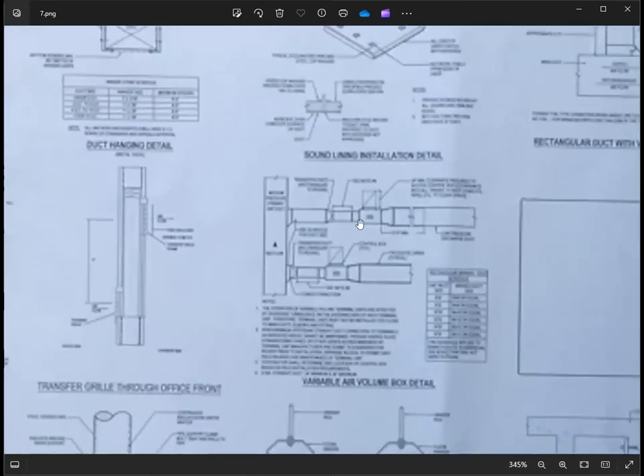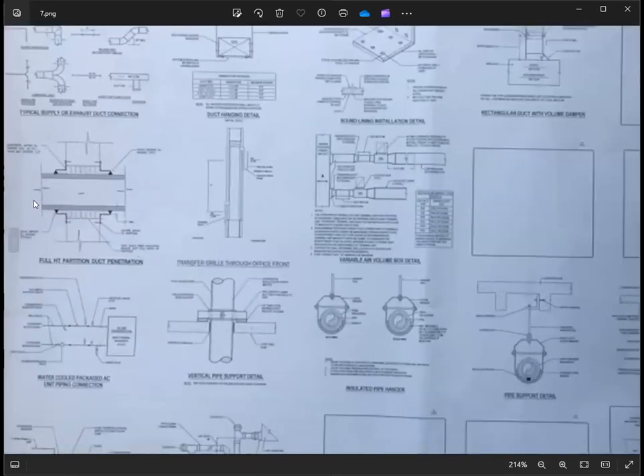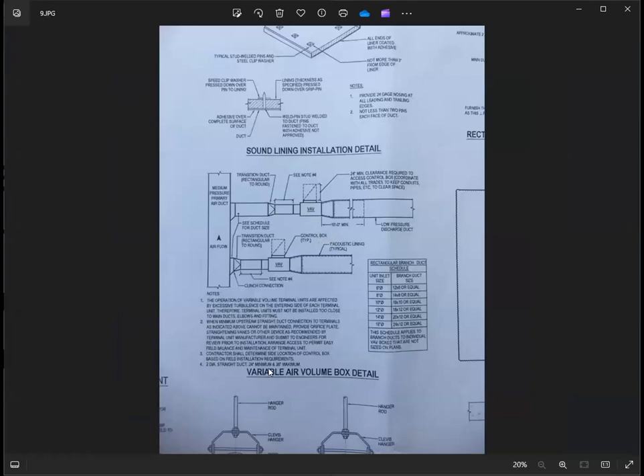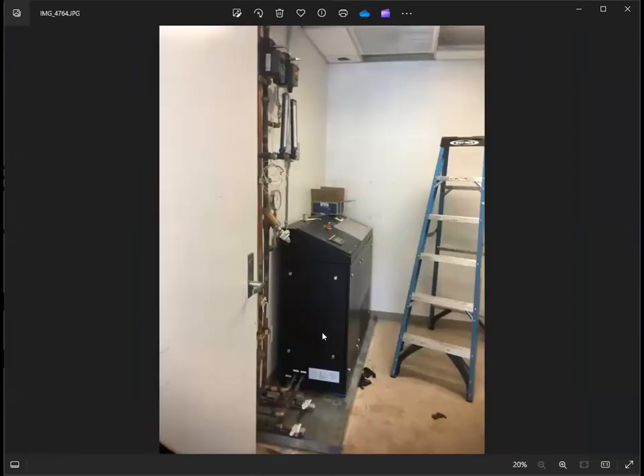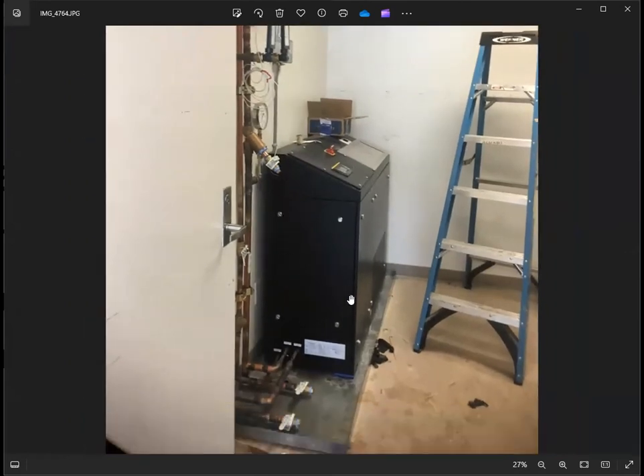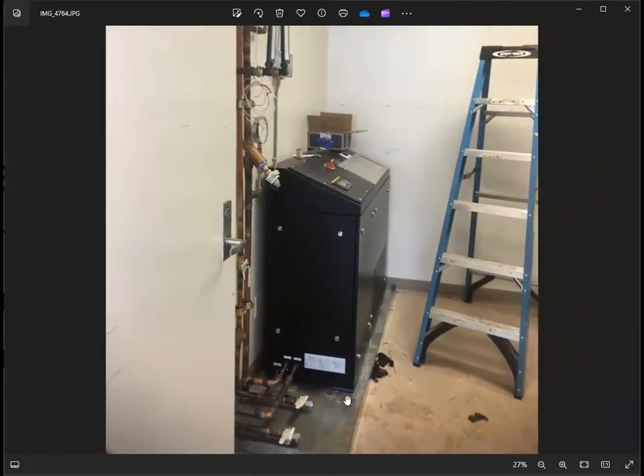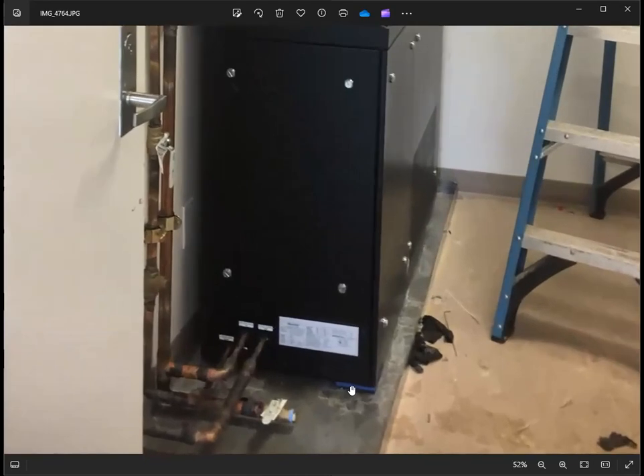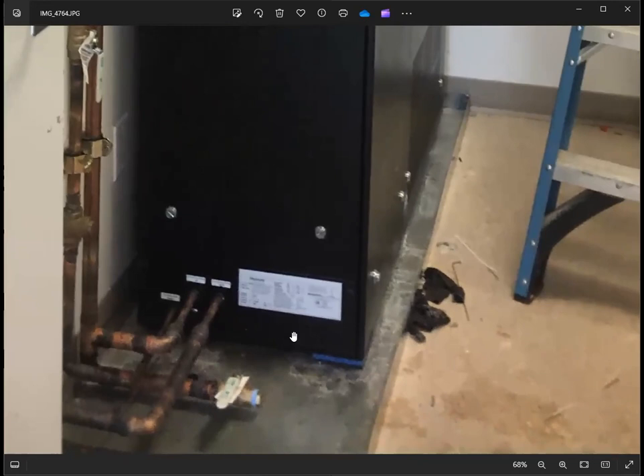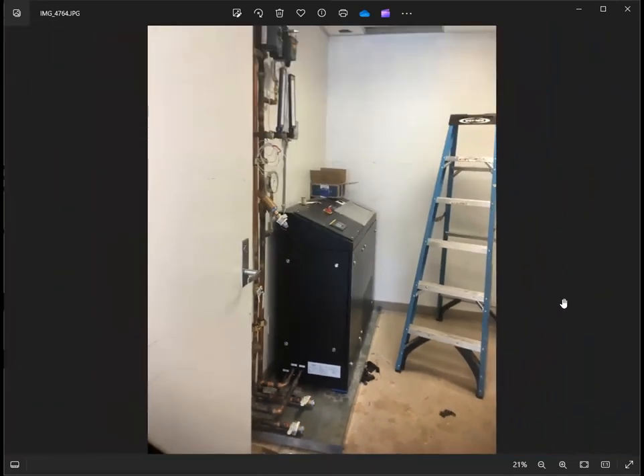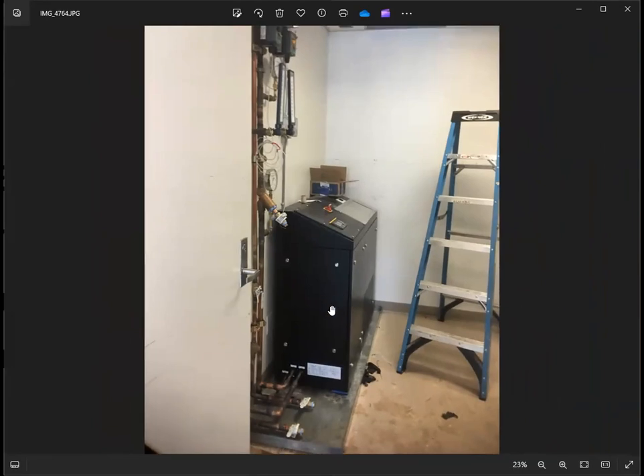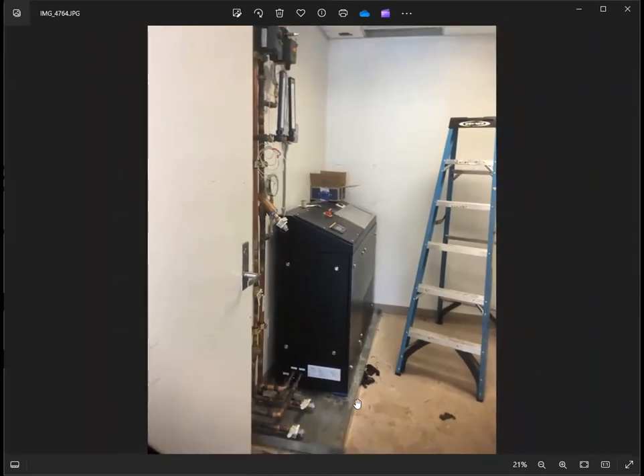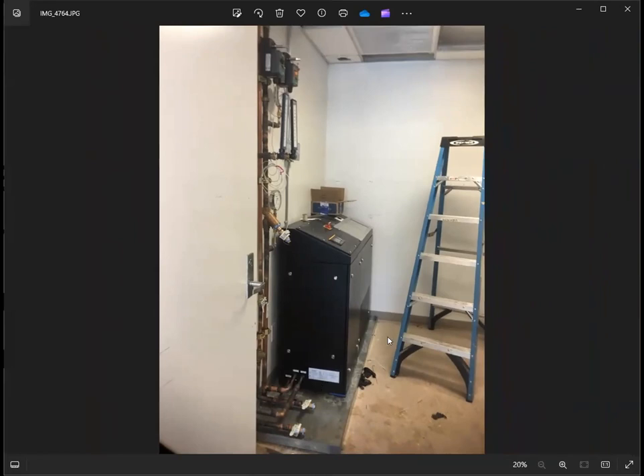This is the supports, hanger supports. It's the VAV box, the penetration in the wall right here. And this is the more visible drawing details for the job. And this is the actual unit. So this is the whole full assembly of the CRAC unit, the AC unit. So take note of how it was installed. Is it a standing unit? Should it be supported? This is a vibration support rubber. Should it be anchored on the wall or on the floor? So you have to review what's recommended in the detail drawings, and also from the submittals of the manufacturer. There are manufacturer recommendations for equipment installations.